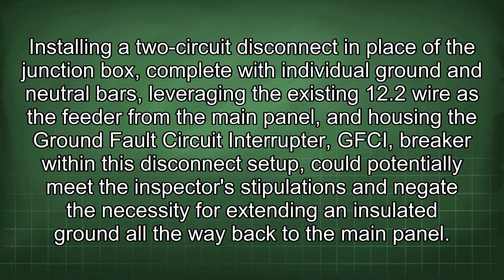Installing a two-circuit disconnect in place of the junction box, complete with individual ground and neutral bars, leveraging the existing 12/2 wire as the feeder from the main panel, and housing the ground fault circuit interrupter (GFCI) breaker within this disconnect setup could potentially meet the inspector's stipulations and negate the necessity for extending an insulated ground all the way back to the main panel.